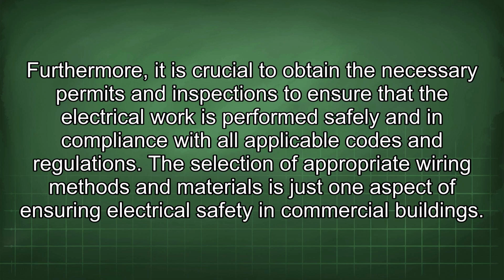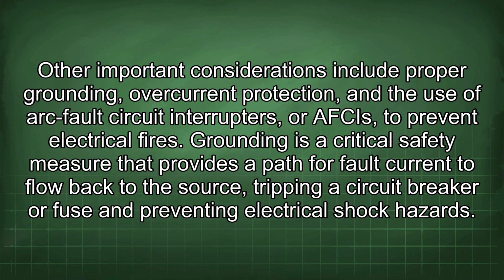The selection of appropriate wiring methods and materials is just one aspect of ensuring electrical safety in commercial buildings. Other important considerations include proper grounding, overcurrent protection, and the use of arc fault circuit interrupters, or AFCIs, to prevent electrical fires. Grounding is a critical safety measure that provides a path for fault current to flow back to the source, tripping a circuit breaker or fuse and preventing electrical shock hazards.